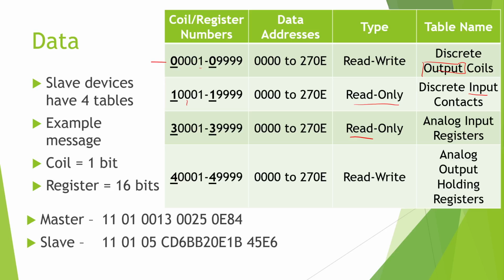But even if you can do it, it basically doesn't affect anything. Same thing is happening here with Modbus. You can say, hey, give me your input values, but you can't set the input values. The output, though, you could say, what is your current output? So you could say, hey, is this output on? So you could read that information from that bank, or you could say, turn this output on. So outputs are read-write, inputs are read-only. It does make sense in the long run.